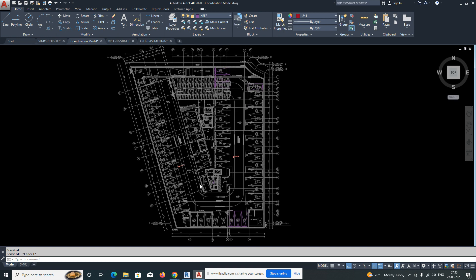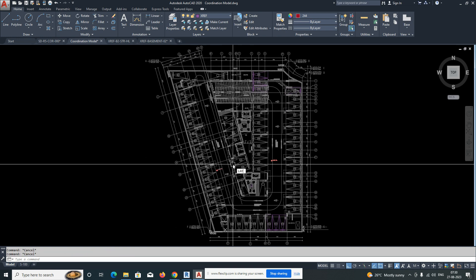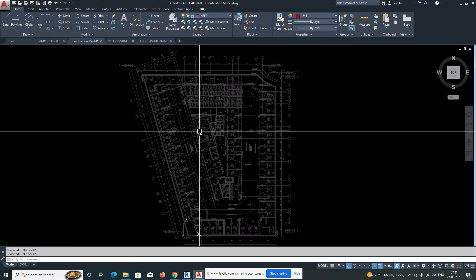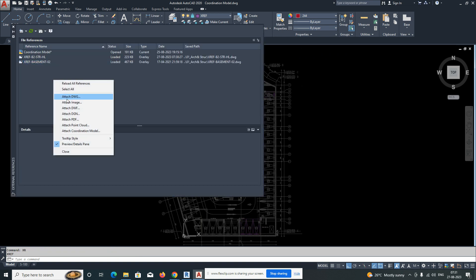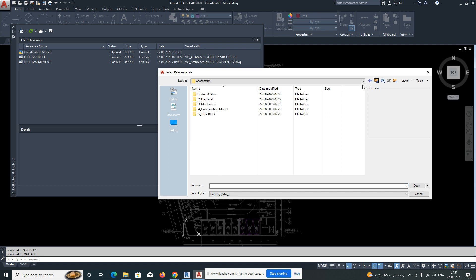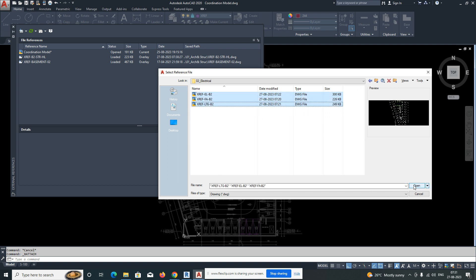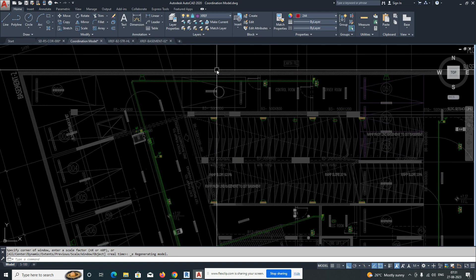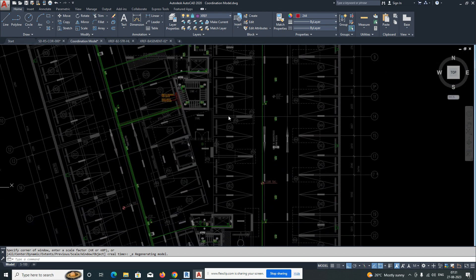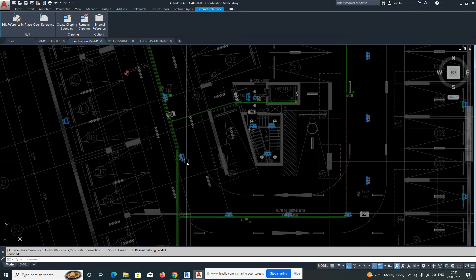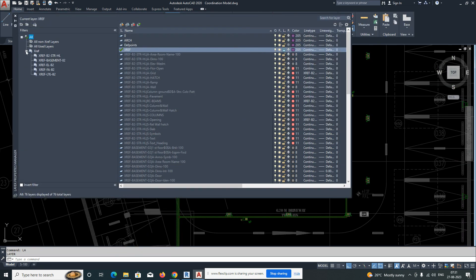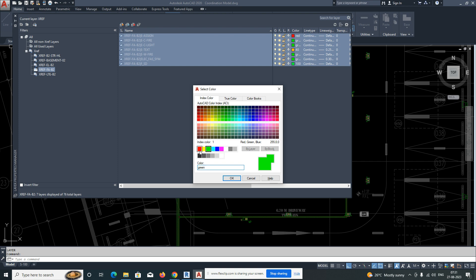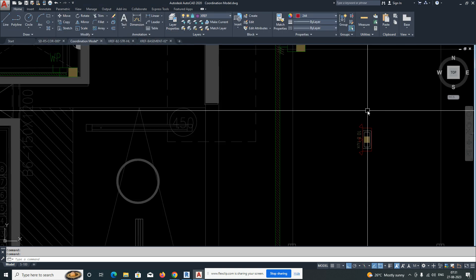The structural and architectural plan are now aligned in the coordination model. Lock those layers. Next step is to attach the lighting and power drawings. Go to the electrical folder, select all the files at once, and click OK. The electrical drawings — including lighting and fire alarm — will appear here. You can change individual XREF layer colors, for example setting fire alarm to red.